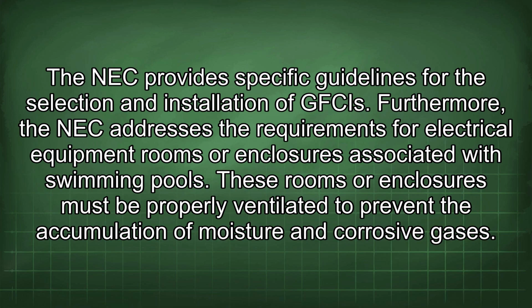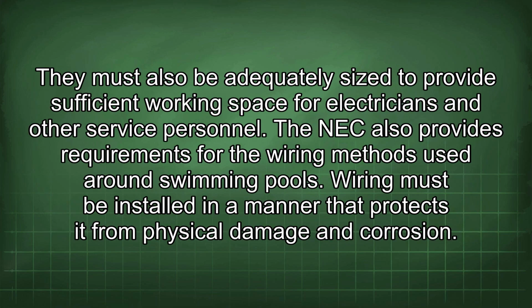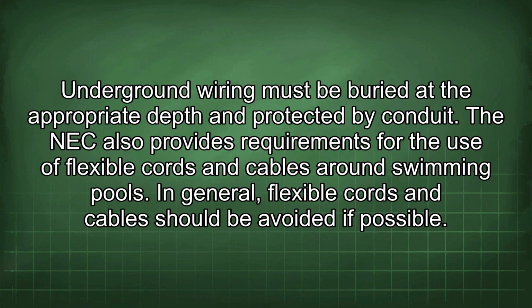Furthermore, the NEC addresses the requirements for electrical equipment rooms or enclosures associated with swimming pools. These rooms or enclosures must be properly ventilated to prevent the accumulation of moisture and corrosive gases. They must also be adequately sized to provide sufficient working space for electricians and other service personnel. The NEC also provides requirements for the wiring method used around swimming pools. Wiring must be installed in a manner that protects it from physical damage and corrosion. Underground wiring must be buried at the appropriate depth and protected by conduit.